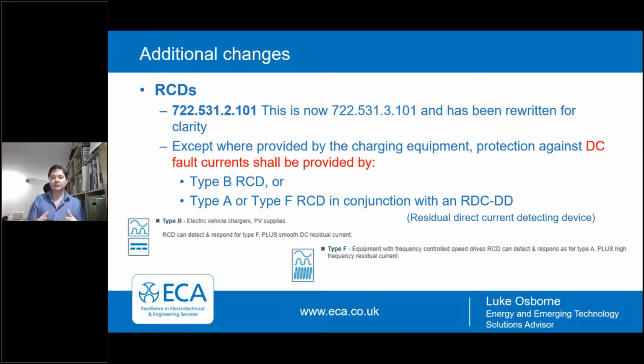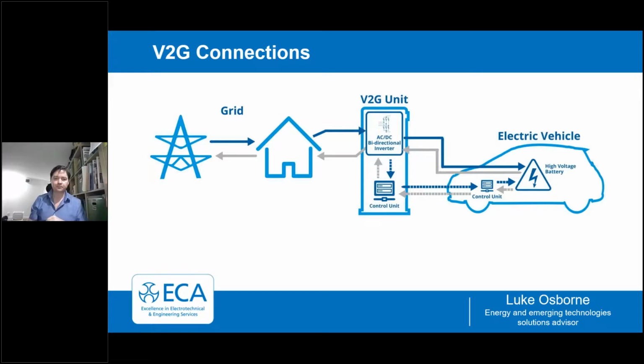So this takes the DC element that's contained within a Type B RCD. So you're not precluded from using a Type A, but you would need to use it in conjunction with the RDC-DD. Again, some of these may be contained within the open PEN protective devices or the EV charge points. Again, it's important that you clarify with the installer what type of protection is being provided.